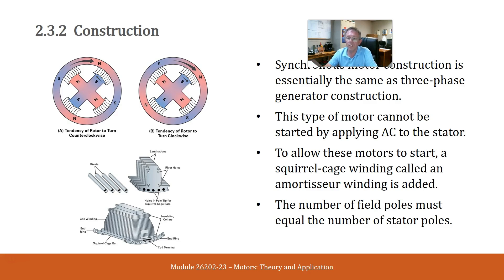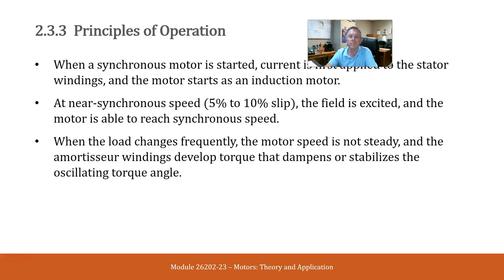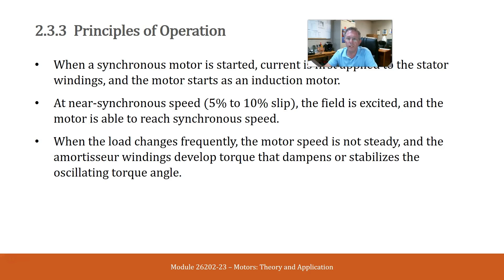The number of field poles must equal the number of stator poles. When a synchronous motor is started, current is first applied to the stator winding and the motor starts as an induction motor. At near synchronous speed — 5 to 10% slip — the field is excited and the motor is able to reach synchronous speed. When the load changes frequently, the motor speed is not steady and the amortisseur winding develops torque that dampens or stabilizes the oscillating torque angle.